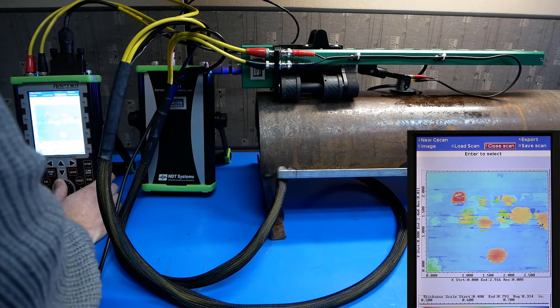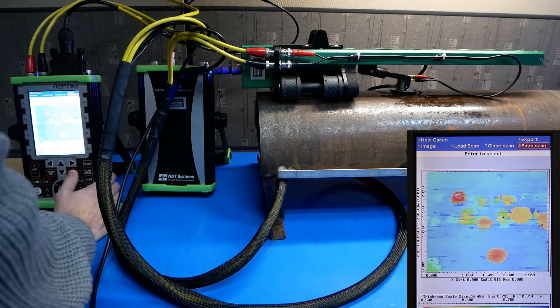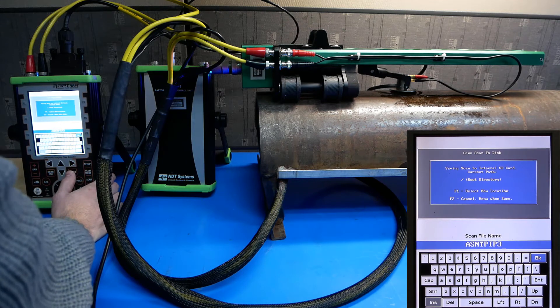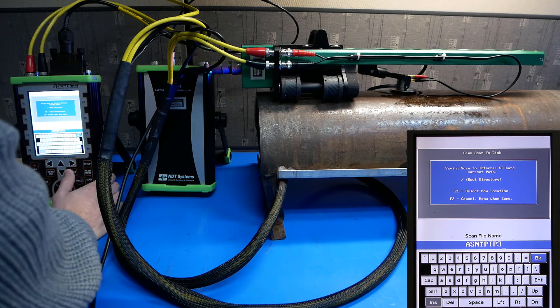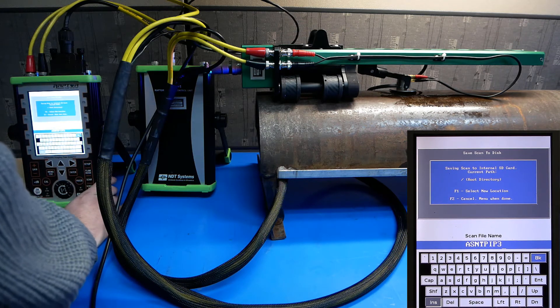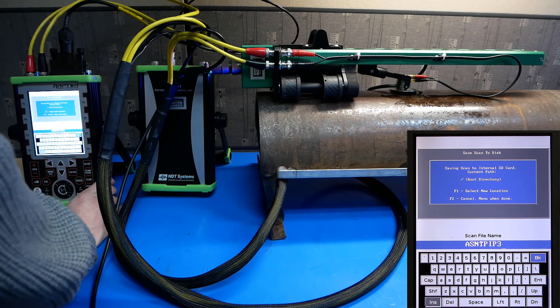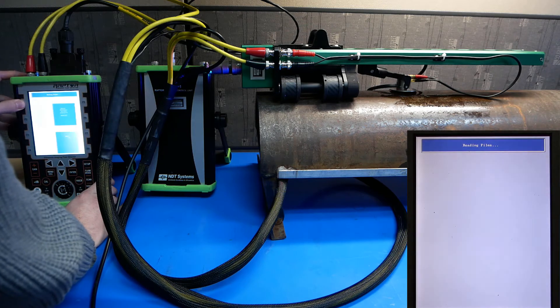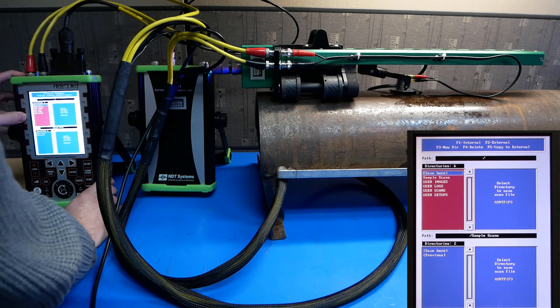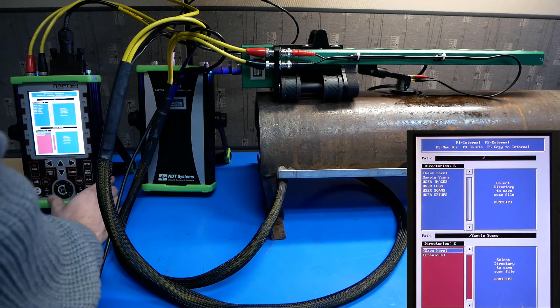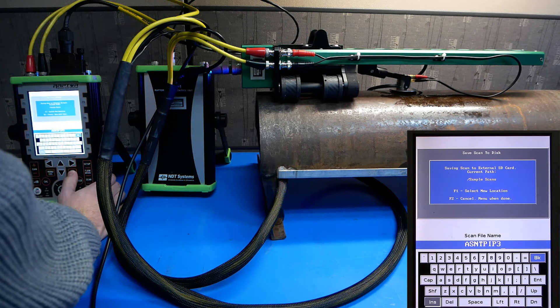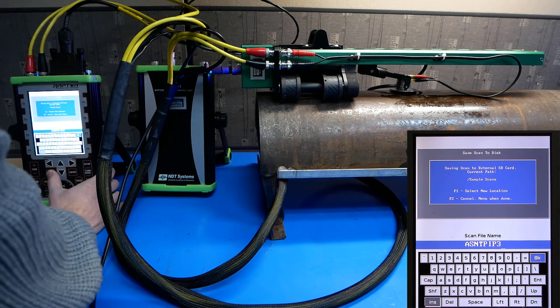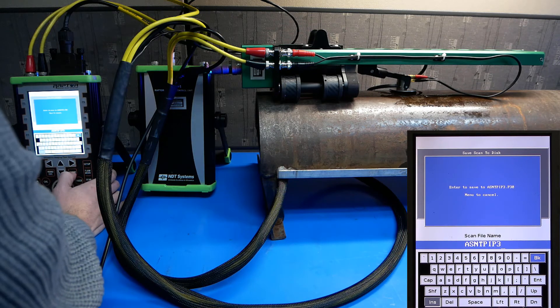We can save the scan by going to option 8, save scan, giving it a name. In this case, ASNT pipe 3. And we can either save it internally or to an external SD card. I'm going to save it to an external SD card. Go to new location, F1. Push F2 to use the external SD card. And push save here to copy it to the external SD card. Hit menu when you're finished. And push enter to save.